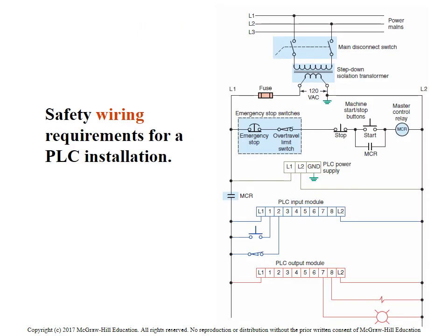And here's a little bit of illustration of that. Here they've got an emergency stop, maybe an over travel switch. It's a little on the light side, but you get the idea. If you hit an emergency stop at this point, it's going to override anything you've got going on here. You drop this out, that's coming out no matter what. At that very moment when that drops out, this drops out. It doesn't allow any input power or output power to the input or output cards.